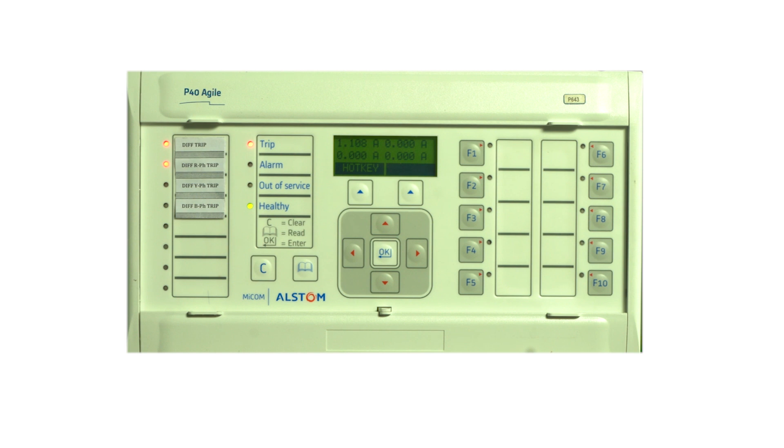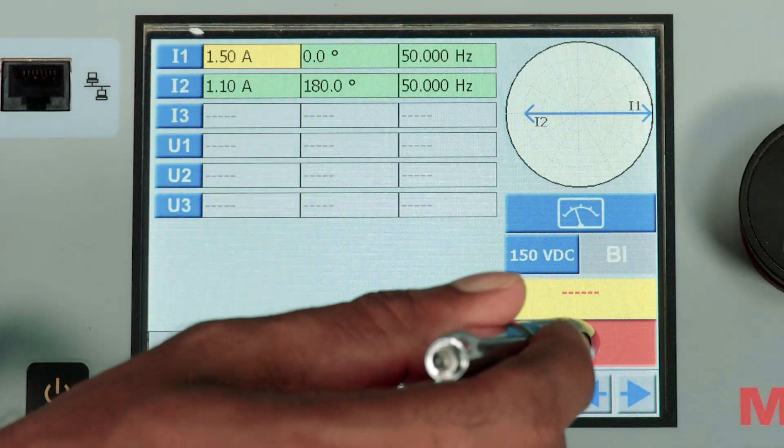Once the relay trips, let's identify what is the differential current. The differential current ID is 0.3 and the corresponding restraint current is 0.996. So let me switch it off.